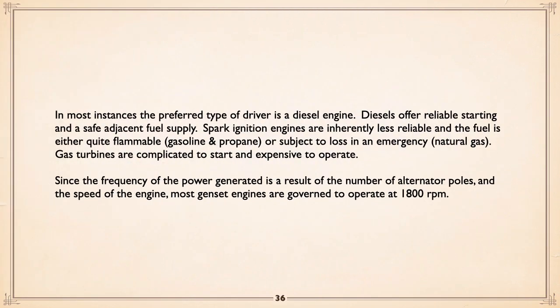Now we get more into mechanical. The preferred type of driver in most cases, diesel. Diesels offer reliable starting and a safe fuel supply. Spark ignition engines are inherently less reliable in terms of starting particularly, and the fuel is either quite flammable, gas or propane, or subject to loss in an emergency, like natural gas. If you're running off natural gas and there's an earthquake, natural gas will be one of the first things to go. Can you power them off gas turbines? They're complicated to start and expensive to run. Yes, you can get a lot of power out of a very small unit. But as a BC Hydro guy once told me, you use them for emergencies and you only run them if you have to because they are expensive.